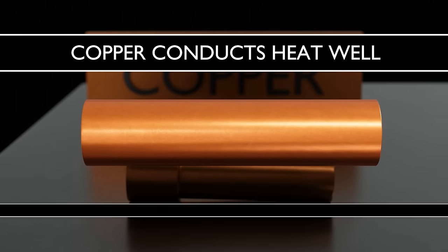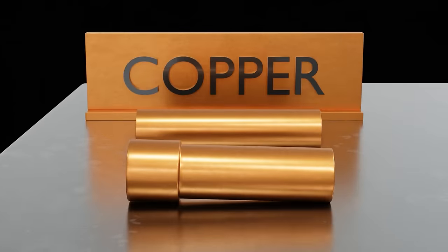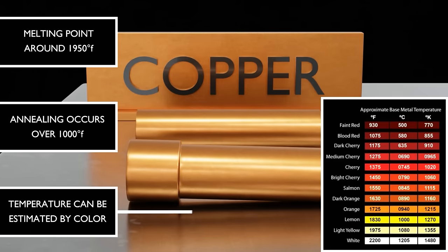Copper conducts heat very well, meaning that heat moves through it easily. It's also flexible and easy to work. You can anneal it, meaning you can heat hard copper to make it soft at over 1,000 degrees. Its temperature can also be easily estimated by color, based on the chart shown here, with dark to medium cherry red being the target color for most alloys.